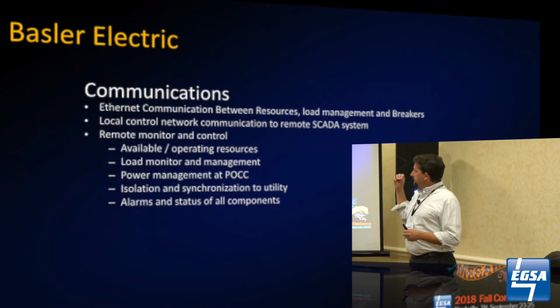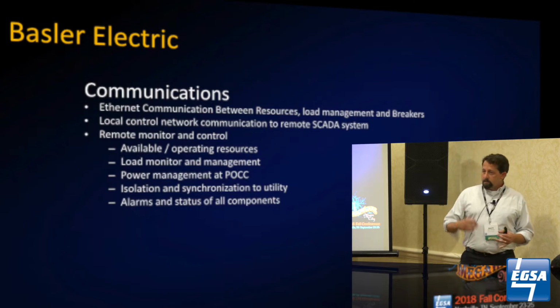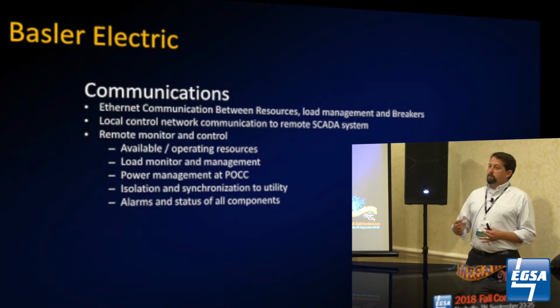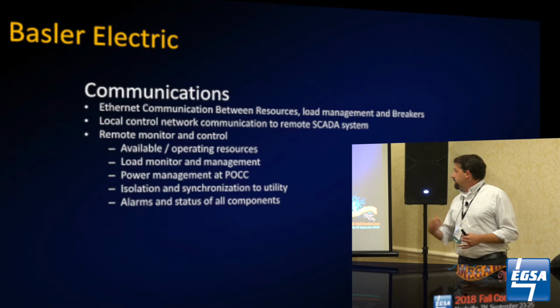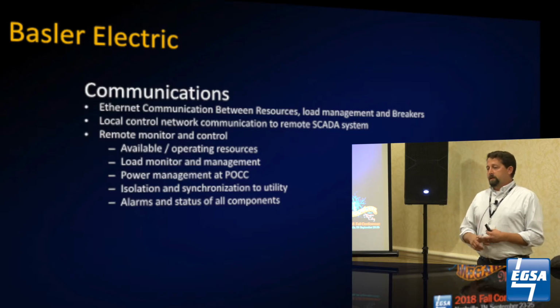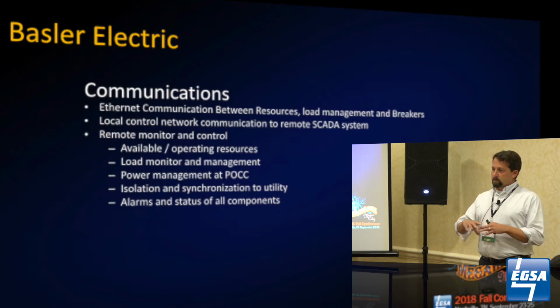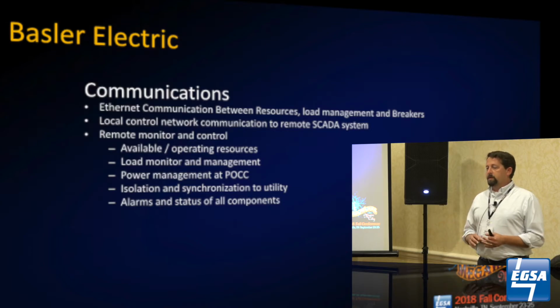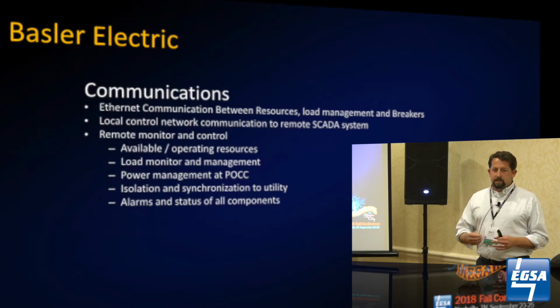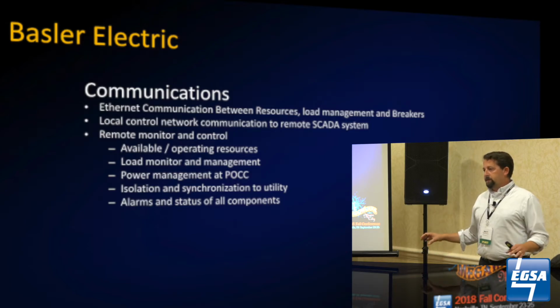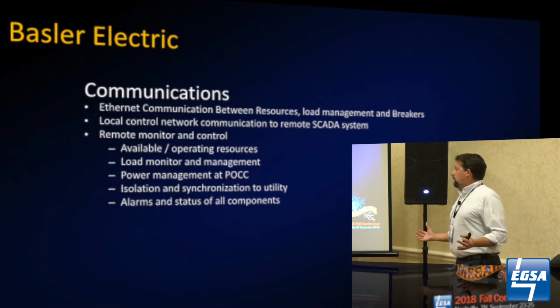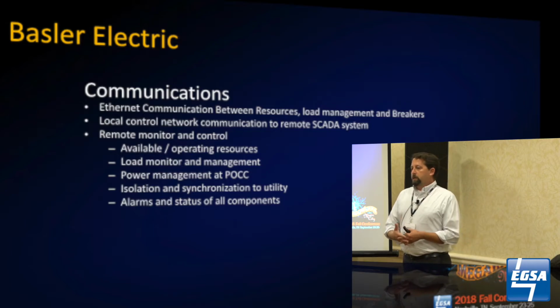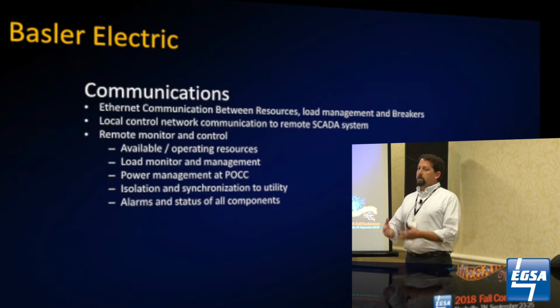The control system and remote monitoring had to be able to isolate in that condition, and also synchronize back into the utility. It also had to look at all the alarms and statuses of all the components located within that grid—all the utility ties, energy resources, loading—and pull all that data back, compile it, and move it into the remote monitoring schemes.